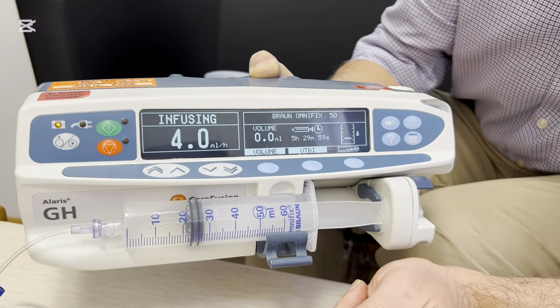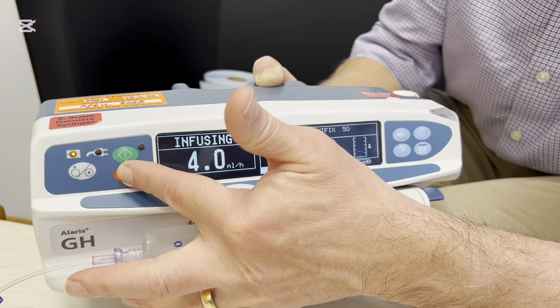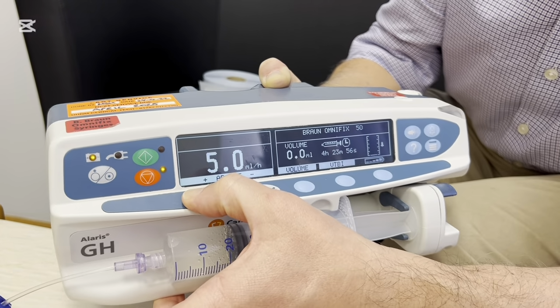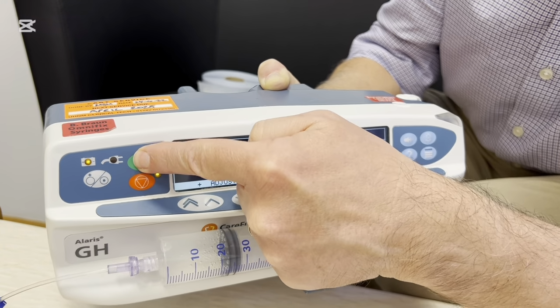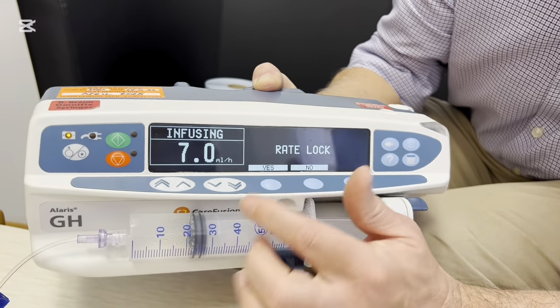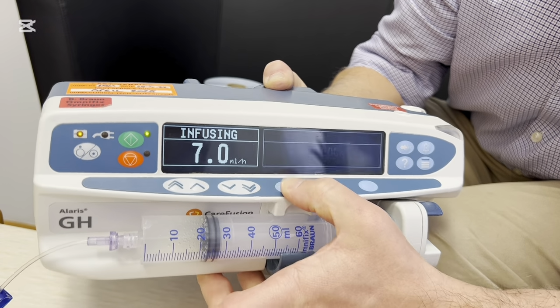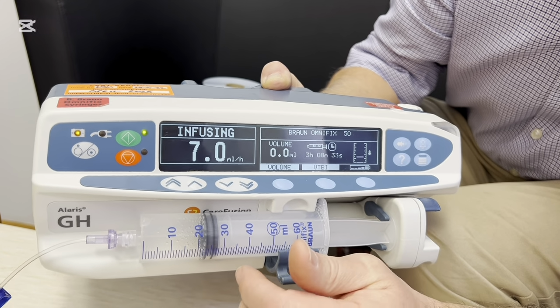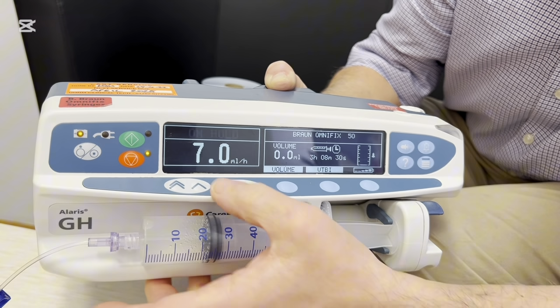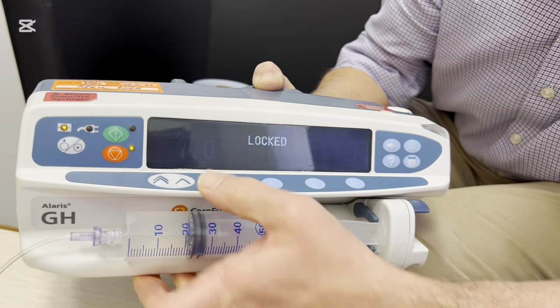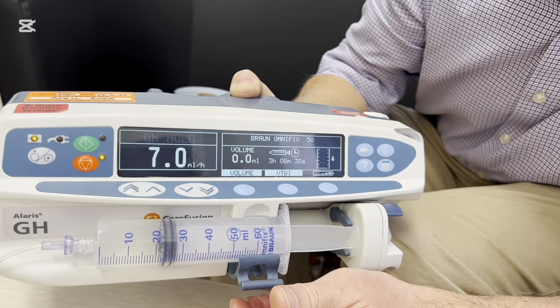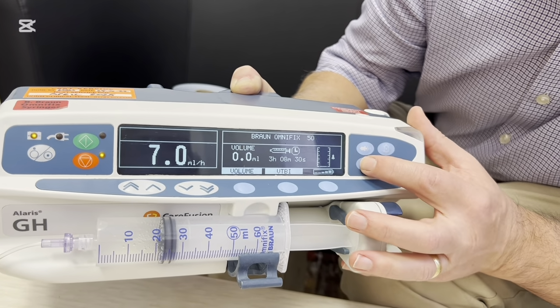If we want to change the infusion rate, we have to pause the device, increase the rate, and press start. Well, let's put a rate lock on this time, so we'll press yes. And this means that when we pause the device, we can't easily change the value. So to get into the menu to unlock it, we need to press the question mark.